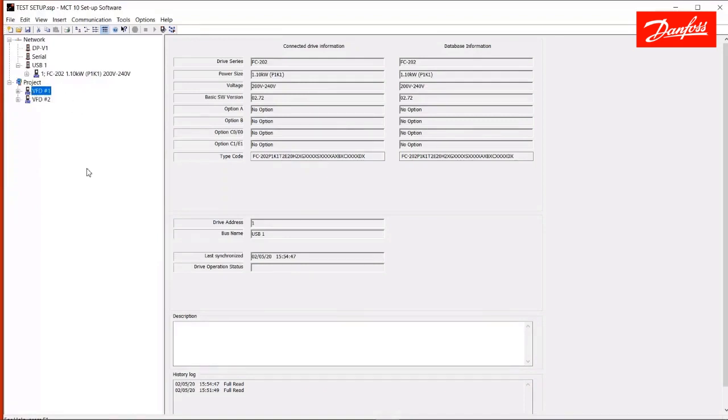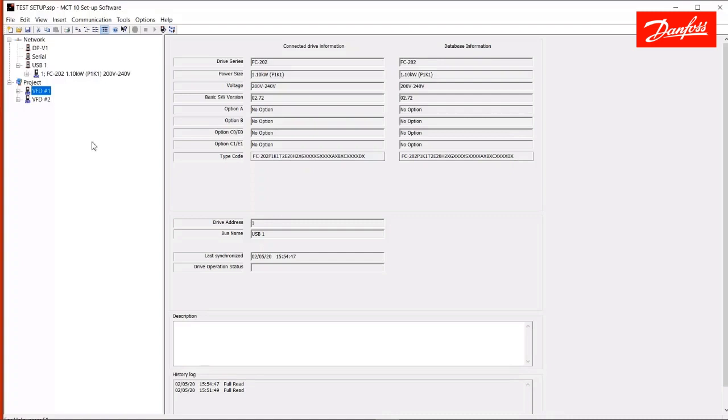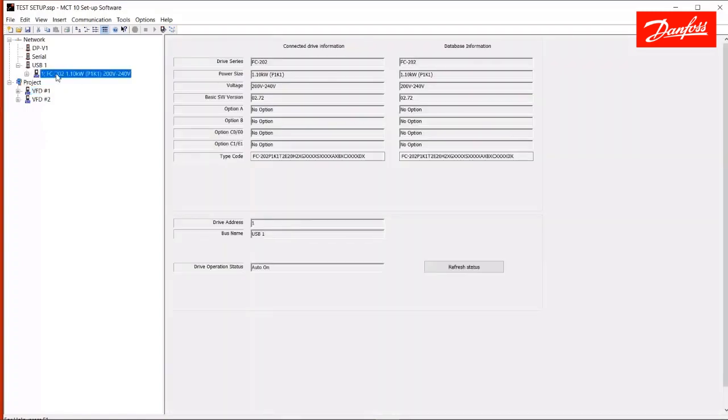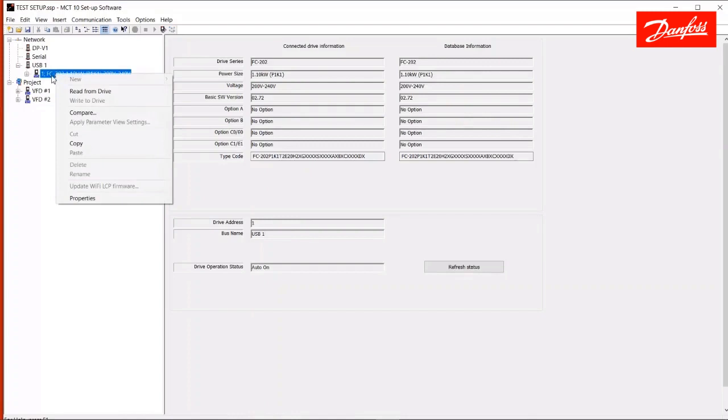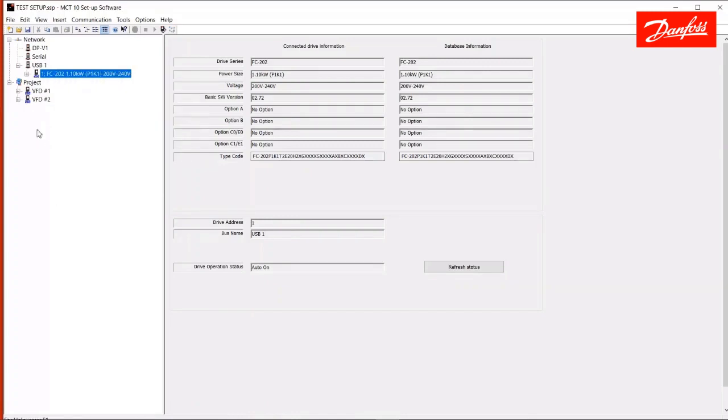So, for example, one thing you can do is make a comparison between two different drives. So, if I had two drives that were acting differently, although they were supposed to be programmed the same, and I wanted to find out what was different between those two drives, I could plug into drive number one. I'm currently set up. Pull it down to the project side, and that'll be this drive here, which I've already done. Then I can go plug into the live drive. It'll appear on the USB side. And you can see here, if I right-click on this drive, I can select Compare.